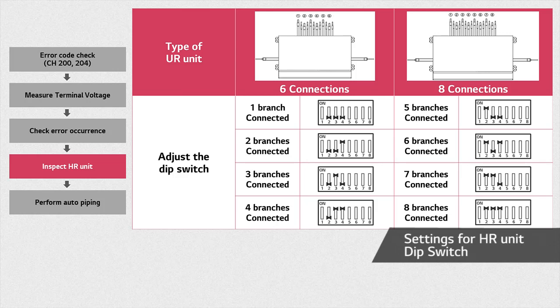Unlike 2, 3, and 4 connection models, in the case of 6 and 8 connection models, switches number 2, 3, and 4 are used. According to the number of connected units, you can adjust the DIP switch referring to this picture. Since an error will occur if this setting is not properly done, make sure you adjust the DIP switch accordingly.